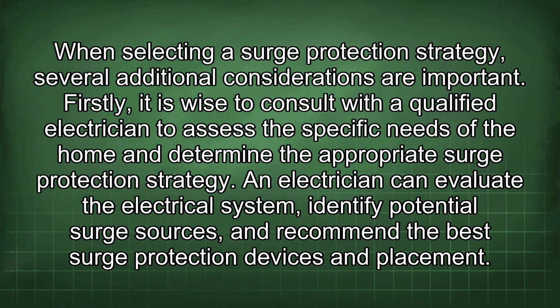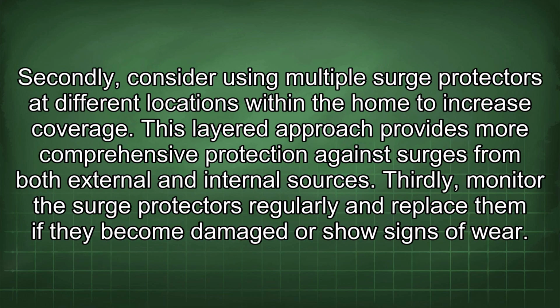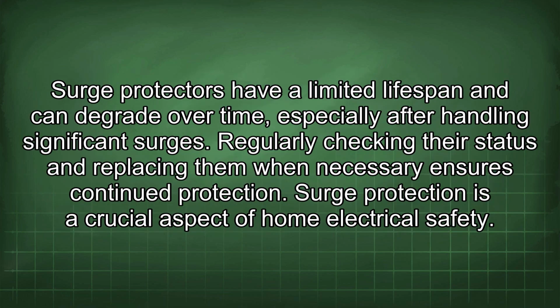An electrician can evaluate the electrical system, identify potential surge sources, and recommend the best surge protection devices and placement. Secondly, consider using multiple surge protectors at different locations within the home to increase coverage. This layered approach provides more comprehensive protection against surges from both external and internal sources. Thirdly, monitor the surge protectors regularly and replace them if they become damaged or show signs of wear. Surge protectors have a limited lifespan and can degrade over time, especially after handling significant surges. Regularly checking their status and replacing them when necessary ensures continued protection.